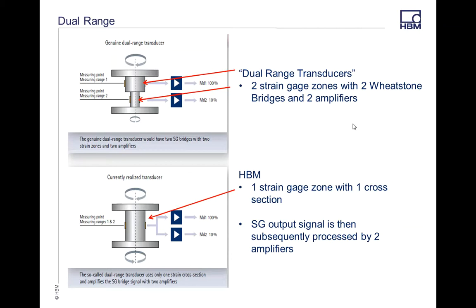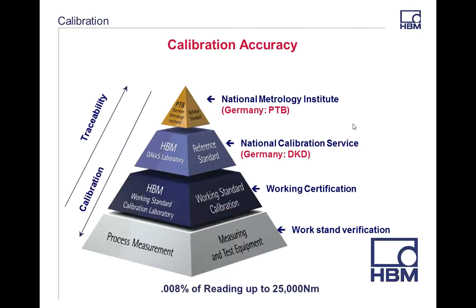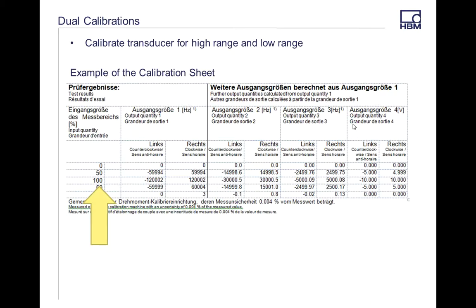So how does this work? If you want to do a dual range on our torque transducers, what you end up doing is you do two separate calibrations. You do one calibration for the full range, and then you do one calibration for the smaller range that you would like. If you wanted a thousand newton meter torque transducer set up to, say 100, you would do two cals. You would do one cal at the 100%, and then the other one at the lower percent.